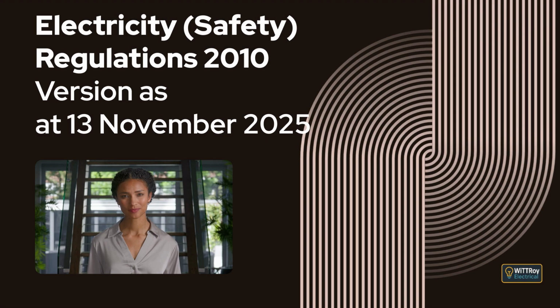The regulation then explains that this frequency requirement may be changed for supplies that are not at standard low voltage, but only if the electricity supplier and the person receiving the supply agree to a different arrangement. The regulation finishes by explaining that a person who supplies electricity commits an offence and is liable to a Level 2 penalty if they supply electricity in a way that does not comply with this regulation.